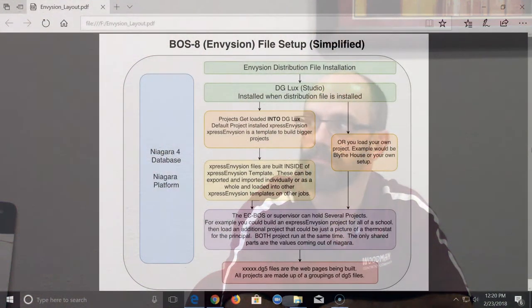Each project is a different hyperlink — a different web address. They run completely independent of each other. For example, Fairfield has multiple projects: a map project showing the campus, a Fairfield High School project, a Fairfield Middle School project. Those all reside on the web supervisor, and if you click on a building you jump to the project inside that EC-BOS. So that school district has four separate projects on it — with three JACEs and a supervisor.